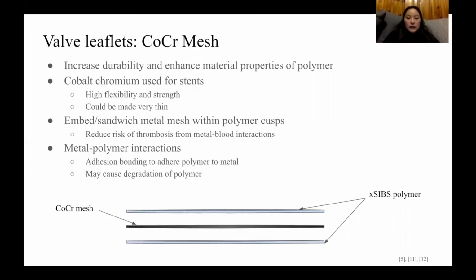In a study that compared several different metal stents, the stent made from cobalt chromium had one of the highest flexibilities and moderate strength. The strength of the mesh can withstand the bending and shear forces, and the very thin nature of both the metal mesh and polymer will ideally allow for these stresses to be minimized and in turn improve durability. The risk of thrombosis is reduced by placing the mesh within the polymer, so there is no direct metal-blood interaction. However, after adhesion bonding of the metal and polymer, the constant stresses placed on the leaflets may cause friction between the two materials and ultimately degradation of the polymer.